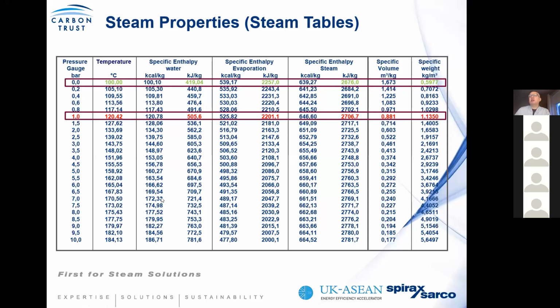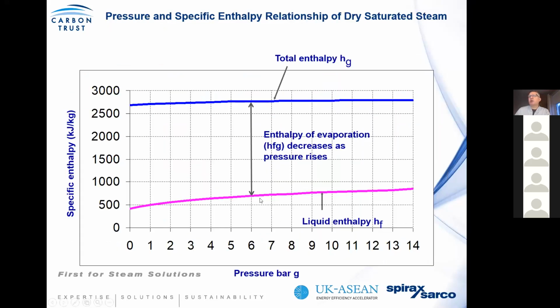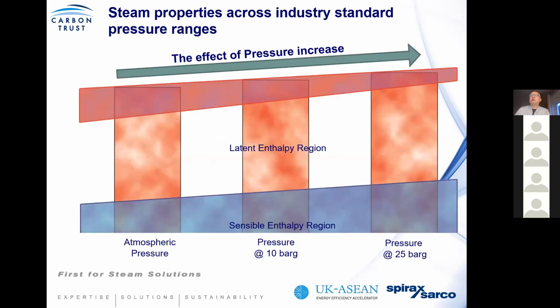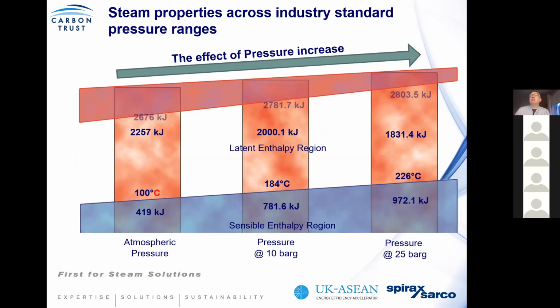So again, looking at a simple chart, as you increase pressure, the total enthalpy of liquid water increases and the enthalpy of evaporation reduces. But although there's a subtle increase in the total enthalpy of steam, it basically stays steady. When we look again at pressure, within your boiler you will generate steam at the required pressure. If we look at different pressures used in industry, we'll see 10 bar, 25 bar, for example. So you can see in this case, we have to increase our water temperature to 184 degrees before we start evaporating. You can also see the different enthalpies of evaporation required to bring it up to dry saturated steam and the total available steam.